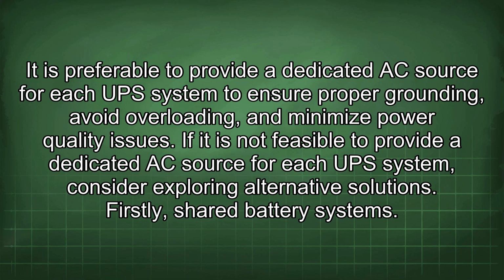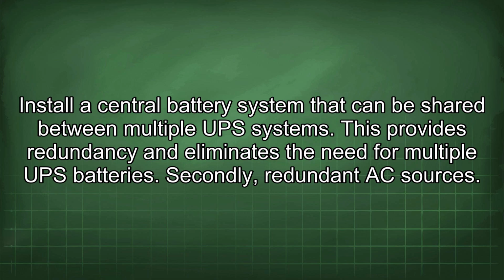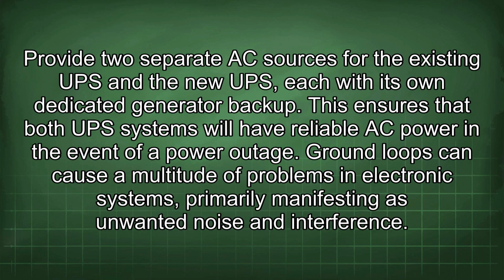It is preferable to provide a dedicated AC source for each UPS system to ensure proper grounding, avoid overloading, and minimize power quality issues. If it is not feasible to provide a dedicated AC source for each UPS system, consider exploring alternative solutions. Firstly, shared battery systems. Install a central battery system that can be shared between multiple UPS systems. This provides redundancy and eliminates the need for multiple UPS batteries. Secondly, redundant AC sources. Provide two separate AC sources for the existing UPS and the new UPS, each with its own dedicated generator backup. This ensures that both UPS systems will have reliable AC power in the event of a power outage.